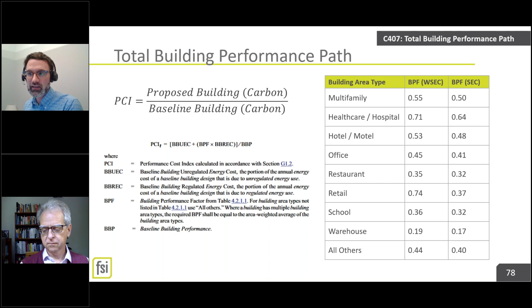Next slide. It's got those same carbon multipliers we talked about before, where electric resistance is worse and heat pumps always win, but they also have a UA backstop—that's U-factor times area. Straight out of the last session: you only get to go so far beyond 20% for Washington, and 0% for Seattle, for extra UA.